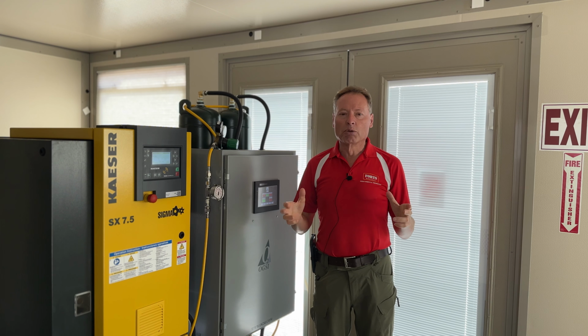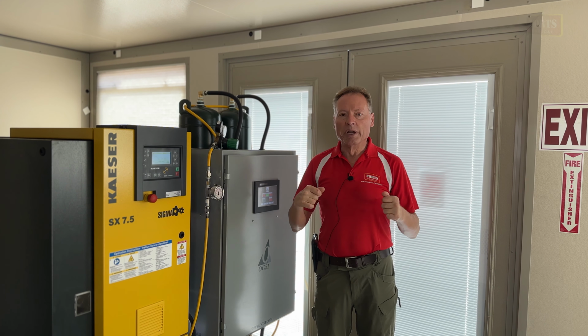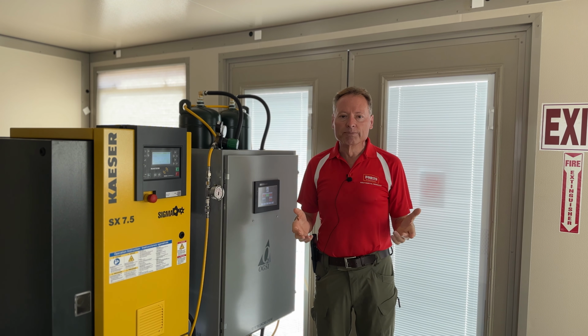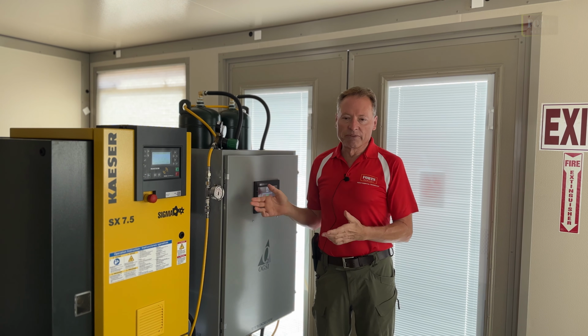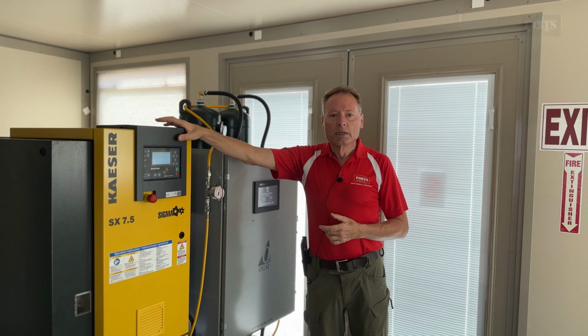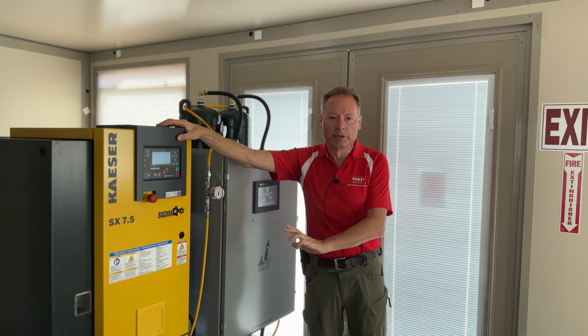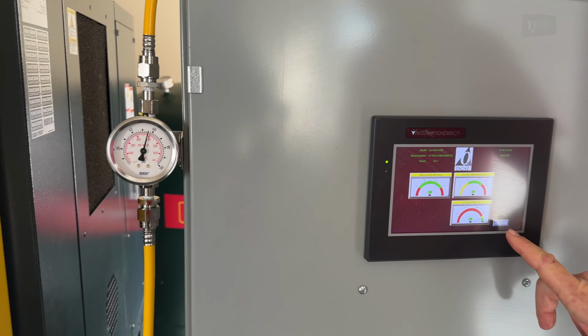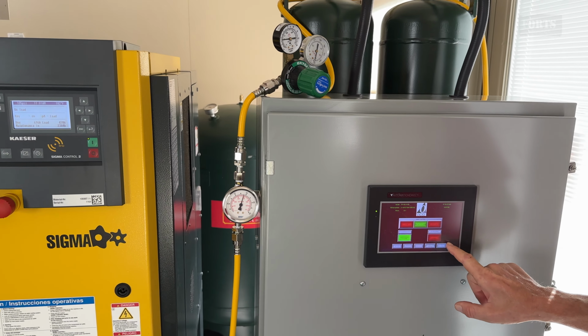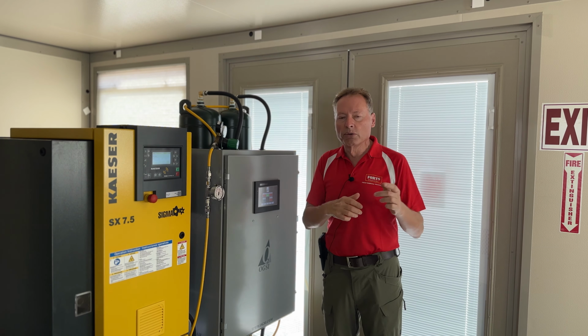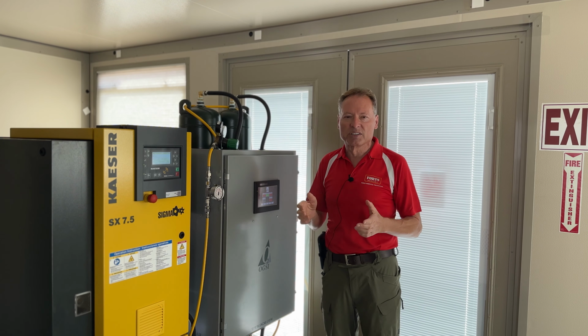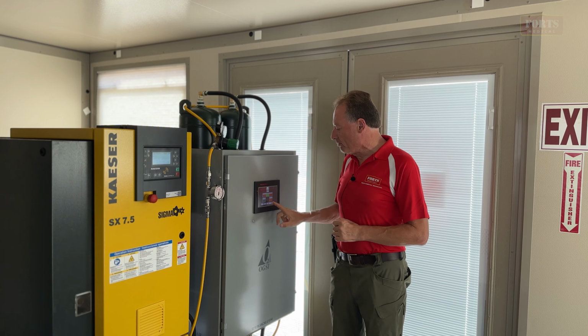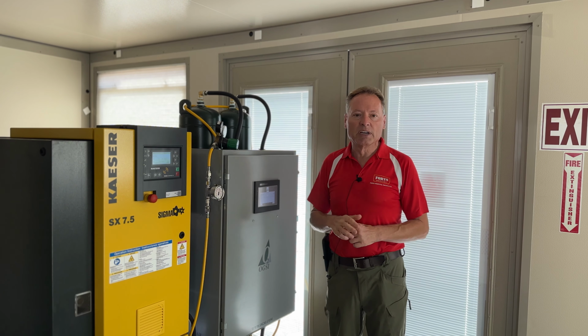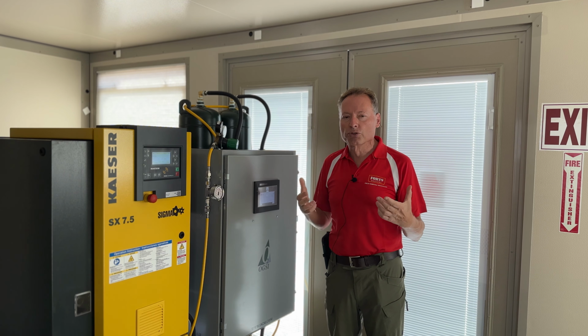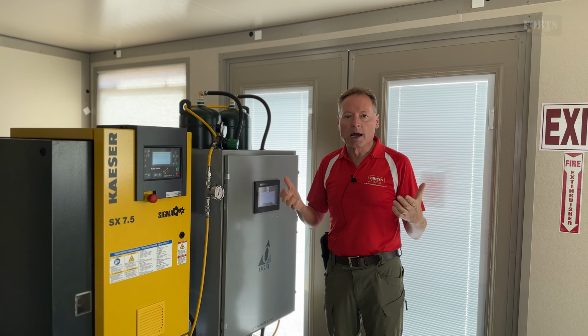Welcome inside the technical pod where we produce medical gas for the hospital. So this hospital is totally self-sufficient. We produce our own power, we treat our own water, we fabricate oxygen with these devices. So this is a medical air compressor that provides medical air inside the unit after being filtered. And then this is an oxygen separator. The oxygen separator takes the medical air and leaves only the oxygen to be vented to the hospital. So we produce about 94 to 96% oxygen, and we constantly verify the quality of the oxygen that we produce. So there's a lot of quality control built into these machines, but they basically operate on their own.